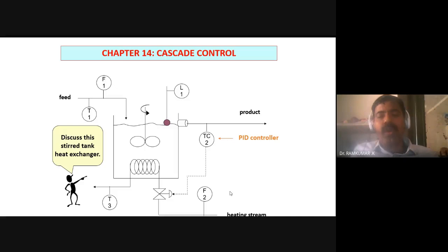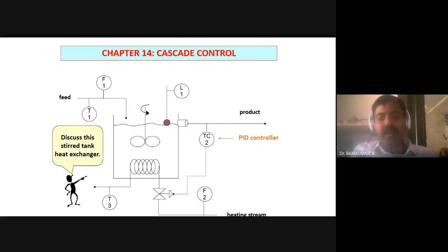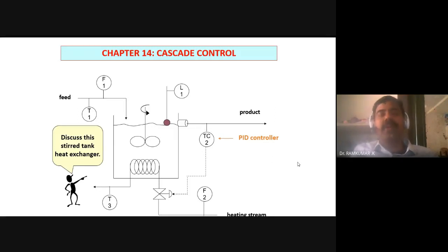Why do you call it a disturbance? Because initially the temperature controller, in order to maintain a given temperature, has opened the valve to a certain specific limit based on the control algorithm. You have opened the valve and everything is going fine — temperature is maintained at the desired value. Suddenly there is a drop in pressure. For the same amount of valve opening, because of the variation in the heating stream flow, the amount of heat transferred to the system is going to get varied and because of that the temperature is going to vary. This is a very important idea in any chemical process industry — disturbances somehow we need to take into account.